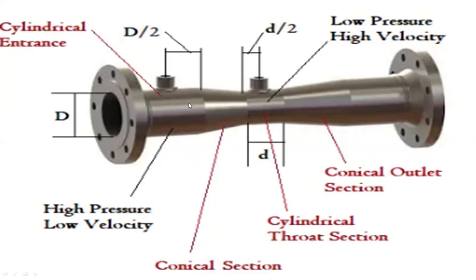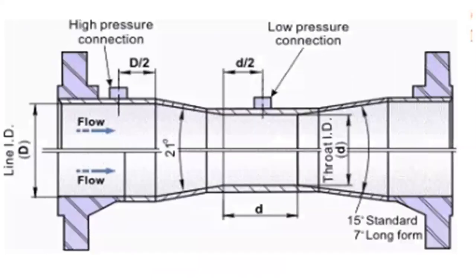In the convergent conical section, the venturimeter tube diameter gradually decreases. The conical angle is normally 21 degrees plus or minus two degrees. While the liquid flows inside the venturimeter, the velocity of fluid increases at the expense of a decrease in pressure. Then in the cylindrical throat, the diameter d consists of the minimum venturimeter diameter. In the throat section, the velocity is maximum and the pressure is minimum. Normally, the throat diameter is one-third or one-fourth of the inlet pipe diameter.